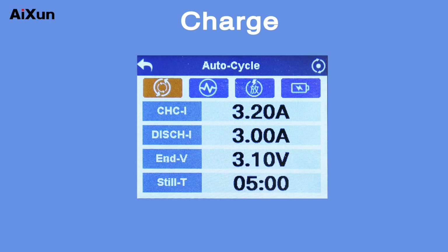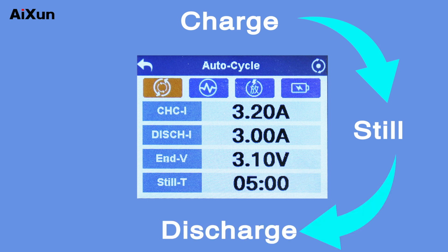The charging state of auto cycle starts by default. The charging current is the one that is set in the auto cycle interface. When the battery is fully charged, it switches to the rest state. The rest time is the one that is set in the auto cycle interface. When the rest time is reached, the battery will switch to the discharging state.